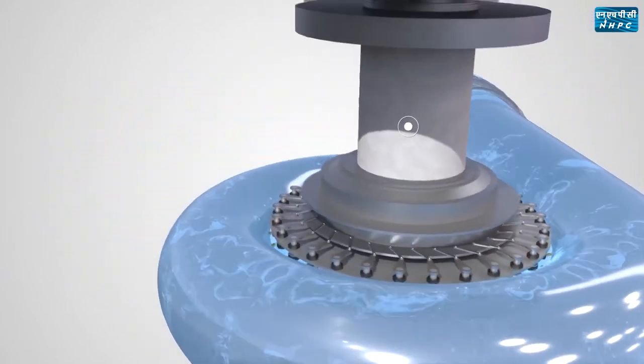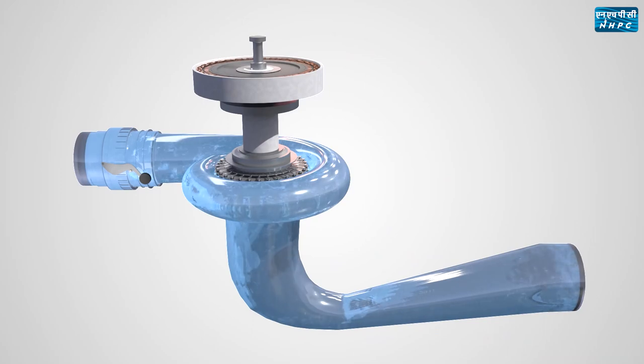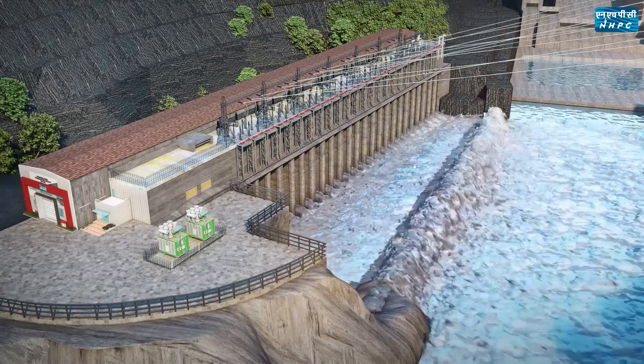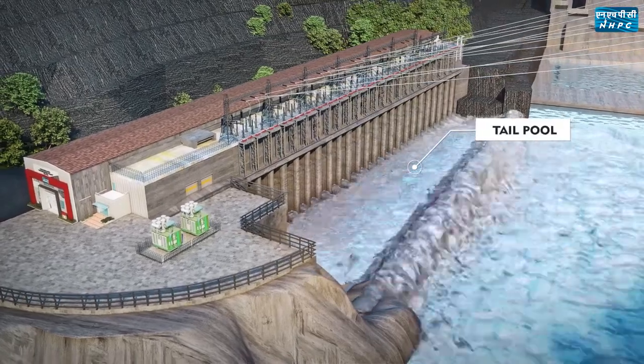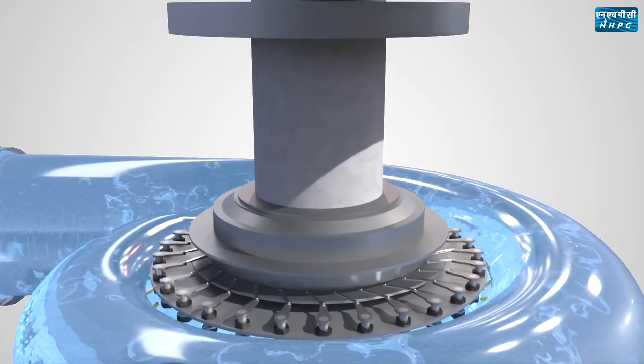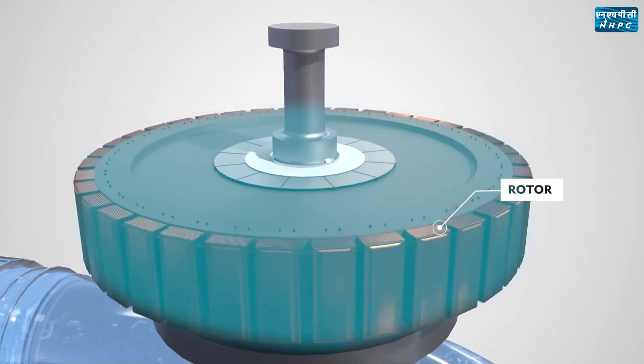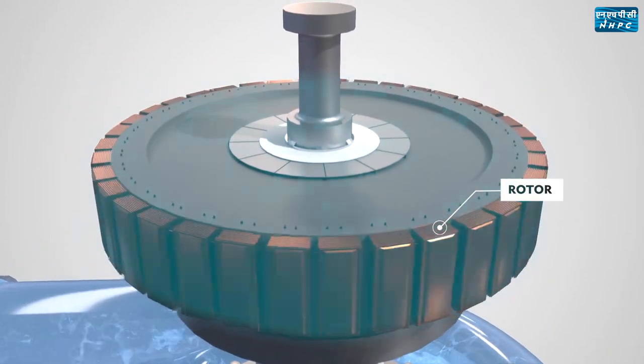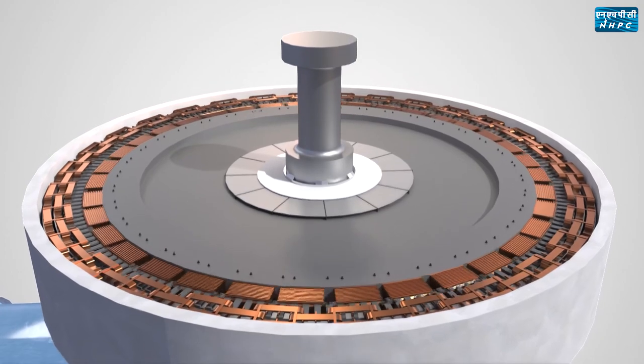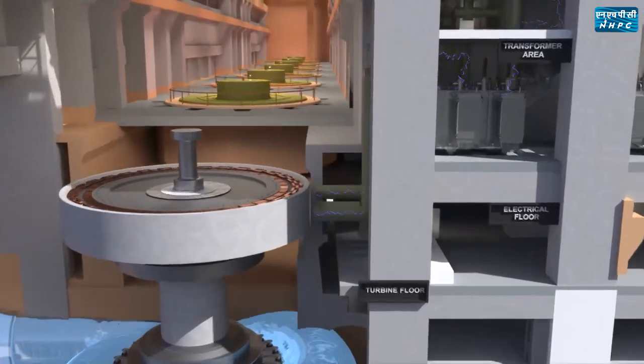The runner is coupled to the turbine shaft. Due to the water flow, the runner rotates, thus rotating the turbine shaft. Water after passing through the runner is channelized through the draft tube and TRC to exit into the tail pool. The rotating turbine shaft is coupled to the shaft of the generator rotor — the biggest rotor ever handled in a hydropower plant — weighing 620 ton. This generator rotor creates a rotating magnetic field, which in turn helps in generating electricity through generator stator windings.